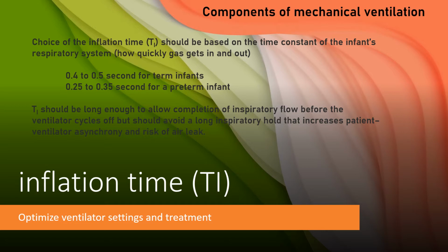Sometimes it is set at 0.4 to 0.5 seconds for term infants and 0.25 to 0.35 seconds for the preterm infant. Inspiratory time, or I time, should be long enough to allow completion of inspiratory flow before the ventilator cycles off, but should avoid a long inspiratory hold that increases patient ventilator asynchrony and the risk of air leak.